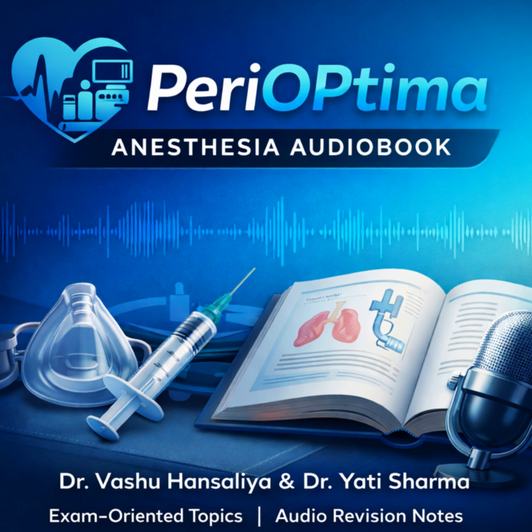First, high level disinfection. This process kills all organisms except for high numbers of bacterial spores. Okay, so it gets close, but not quite sterilization. Precisely. It's used for what we call semi-critical items. And give me an example of a semi-critical item, something we use every day. A flexible endoscope, a fiber optic scope, or a laryngoscope blade. These items touch mucous membranes or non-intact skin, but they don't actually penetrate sterile body tissue.